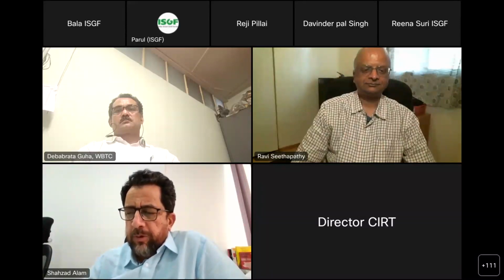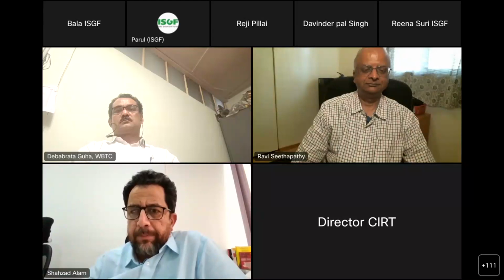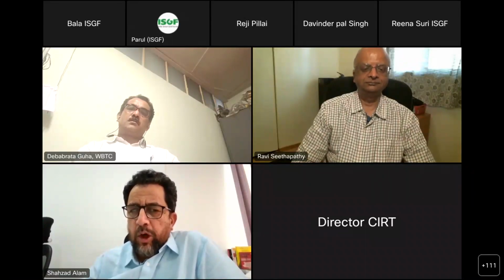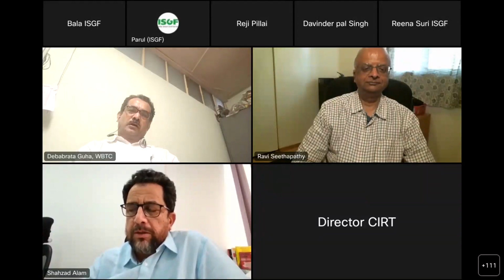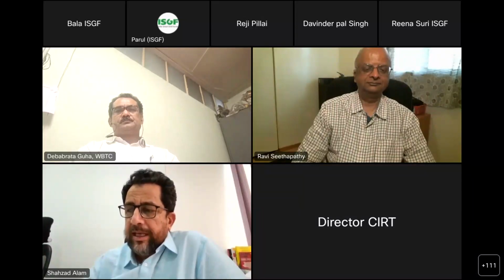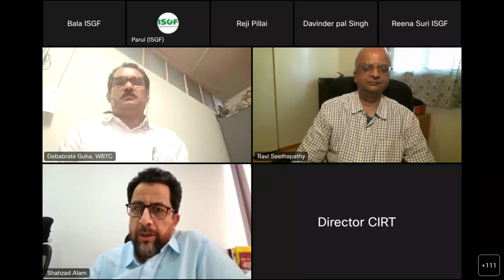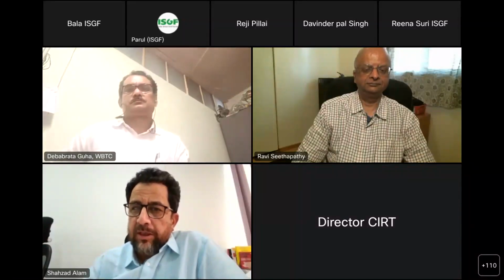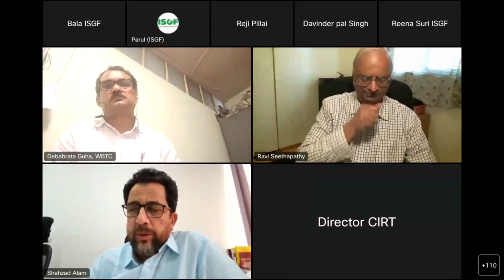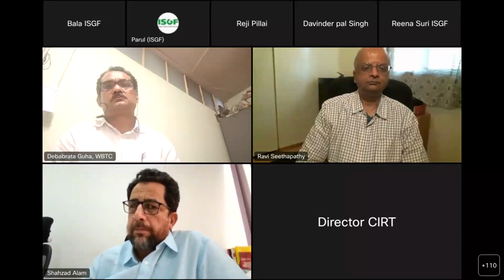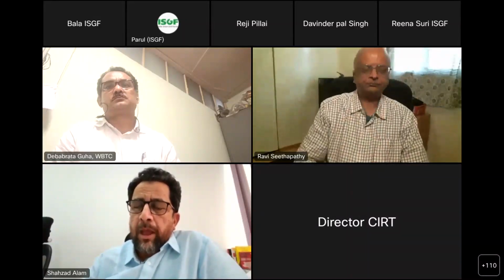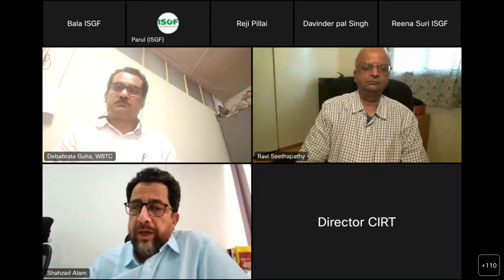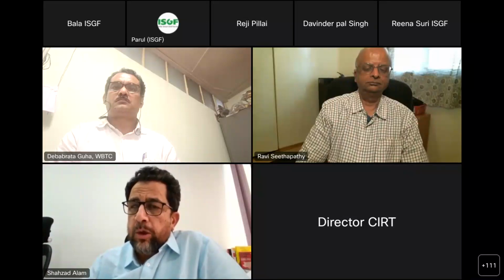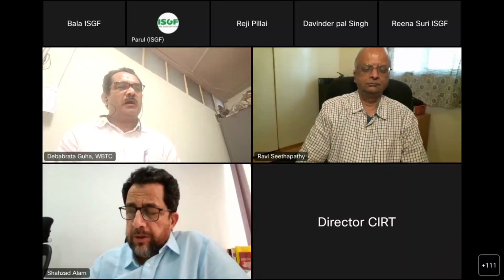You must have noted, Ravi Saab, that we had a lot of RVCs, rapid voltage changes, in Kolkata, whereas we could not find any in Pune. This was because the PQ meter installed was at the 22 kV incomer transformer, while at Kolkata we had it at the 230 volt feeder. Since there was a transformer in between, RVC could not be acquired by the PQ meter. So in future measurements and exercises, we will need to monitor at both ends to get as much information as possible.